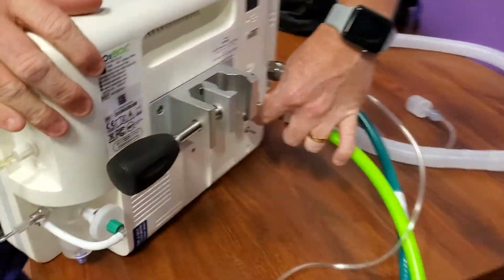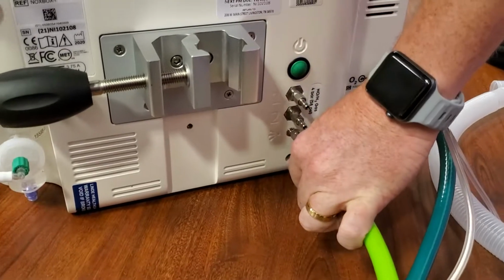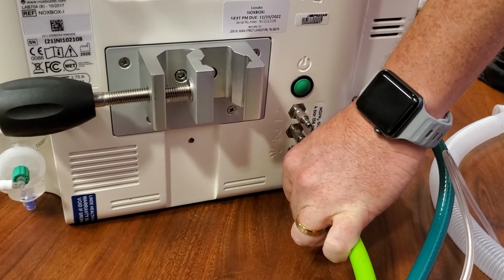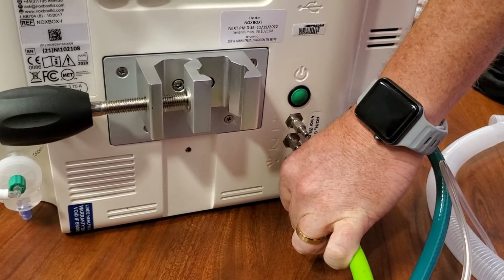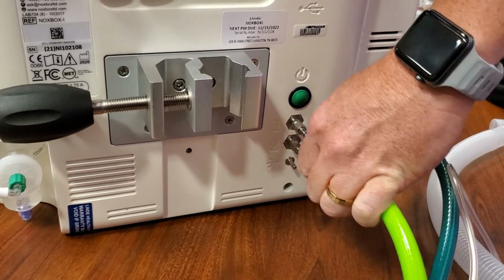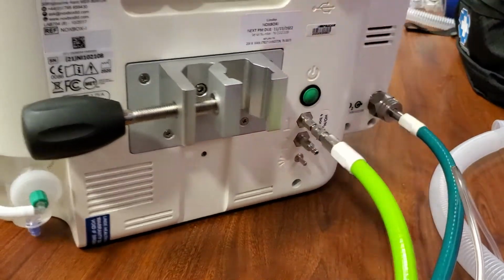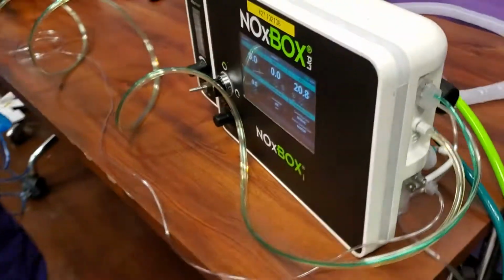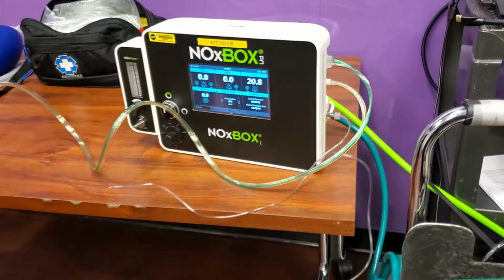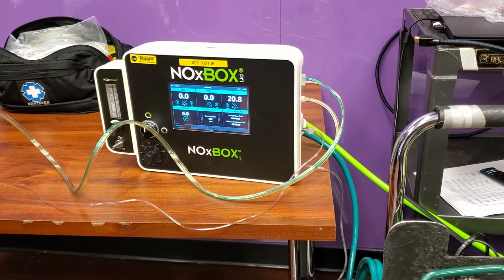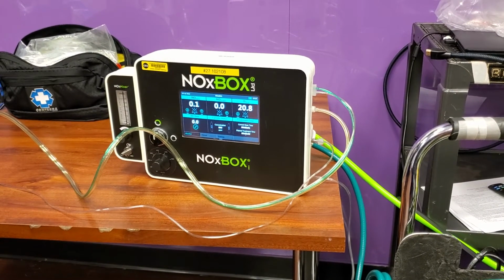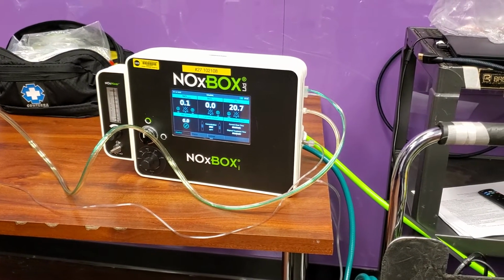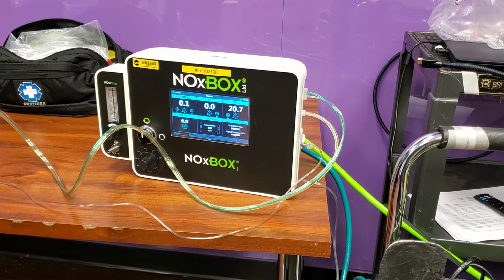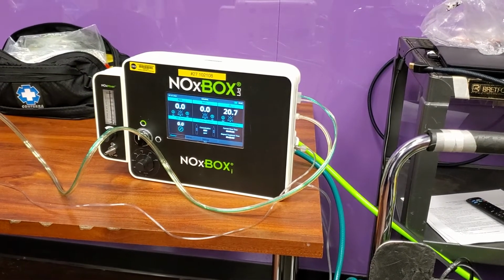Once that's fully closed, we're going to disconnect our tubing here, and we're going to purge the line on our bottom one. Once that's purged, we're going to place this back on number 1 here. Now it's not going to expect there to be any nitric or vent flow coming through it, so it'll sit in standby for as long as you need to prior to hooking it up to the patient there. And I think that just about covers most of our stuff as far as the normal use of the NoxBox.